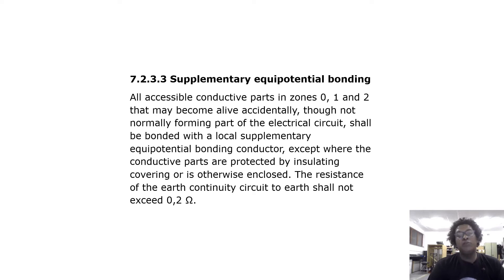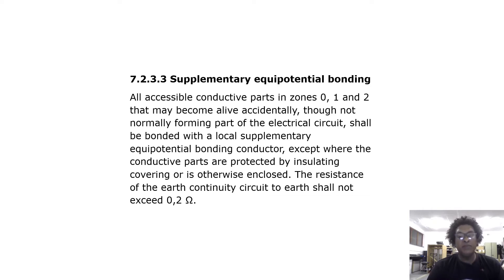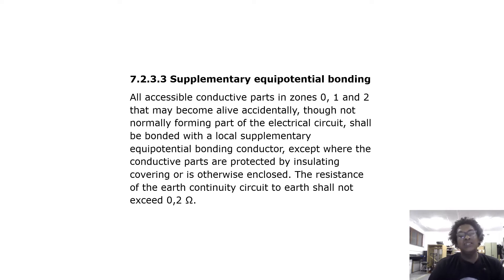Regarding supplementary equipotential bonding: all accessible conductive parts in zones 0, 1 and 2 that may become live accidentally — not normally forming part of the electrical circuit — shall be bonded with a local supplementary equipotential bonding conductor, except where conductive parts are protected by insulating covering or are otherwise enclosed. The resistance of the earth continuity circuit shall not exceed 0.2 ohms.